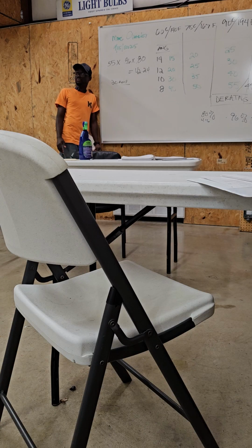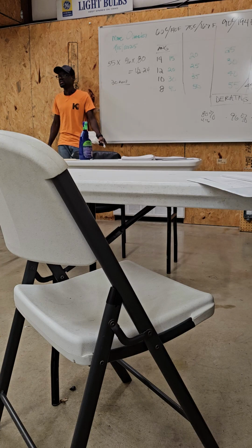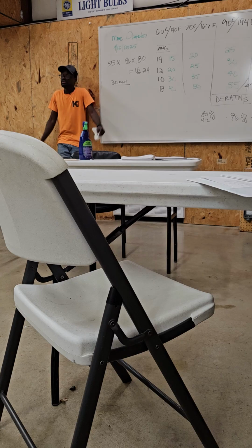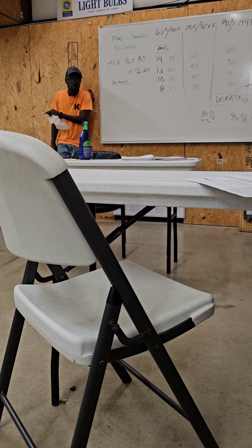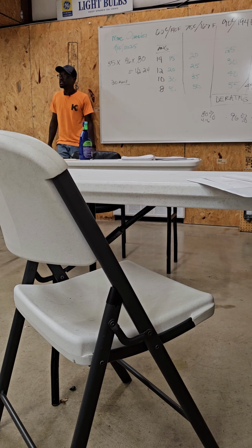I think they were like 1.7 amp per fixture and there were only like 15 of them, something like that. Even if all of them come on at the same time, they're coming from 2 different breakers anyway, I have 2 sets. So I know the most they're gonna pull per breaker is 10 amps. So I know that I am safe. I can just check, done deal.